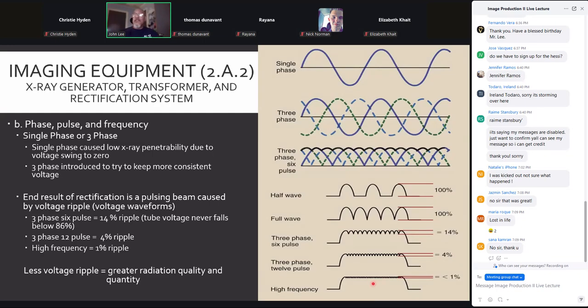By switching to a high frequency generator that uses a bunch of different devices and flattens out the voltage ripple, and there's a bunch of things that go into this, we can go from 60 hertz to 500 up to about 2000 hertz, which causes our voltage ripple to become less than 1%. So from 100 kV max on our machine, only down to just above 99 kV, which again translates to more X-rays being produced per exposure and higher energies of X-rays being produced, which is basically what this line sums up here. Less voltage ripple, greater quantity and quality.